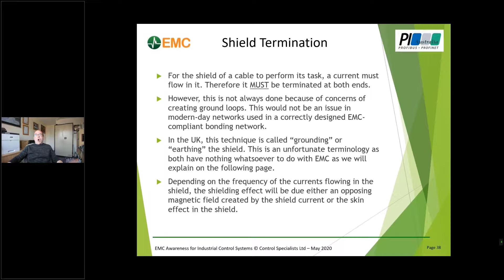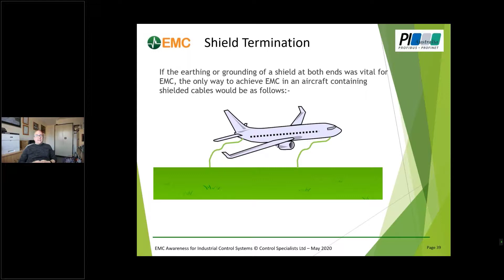I'm led to believe that the new Dreamliner, the Boeing Dreamliner, has actually got PROFINET devices. Well, if those guys have been on the Certified PROFINET Engineer course, or the installer course to be correct, they'll have been told of the importance of making sure the shielded cable is grounded at both ends. Well, in that case, the only way we could achieve that is to purchase a 37,000 foot drum of earth cable, put a weight on it and make sure it's touching the ground at all times. Clearly a complete nonsense. If we didn't have EMC in an aircraft, I don't think many people would fly in it, and I don't remember seeing wires hanging from the bottom. So nothing whatsoever to do with EMC.